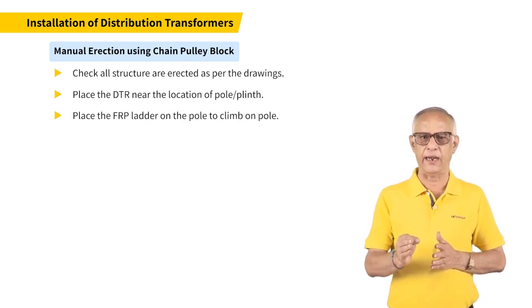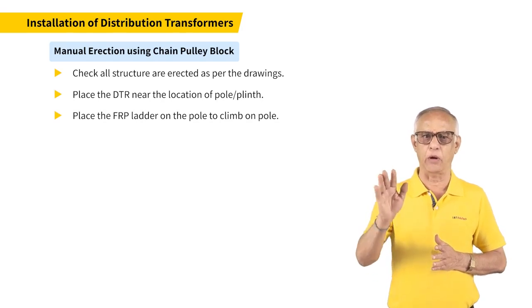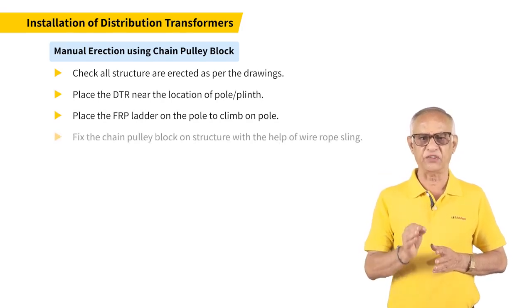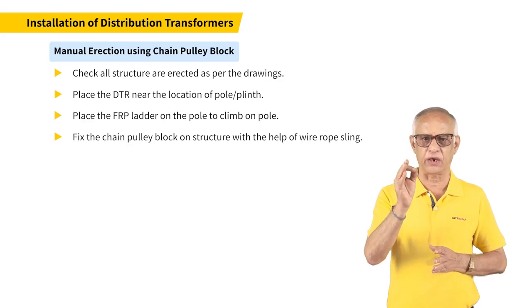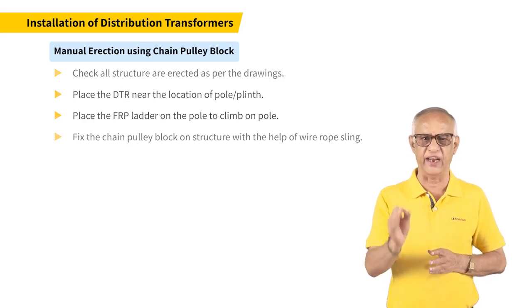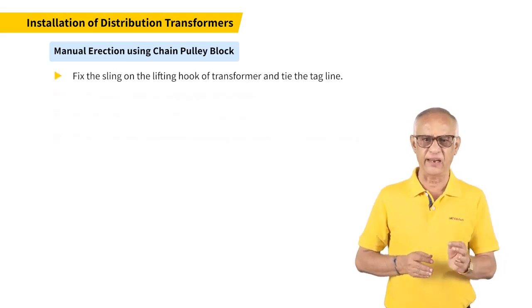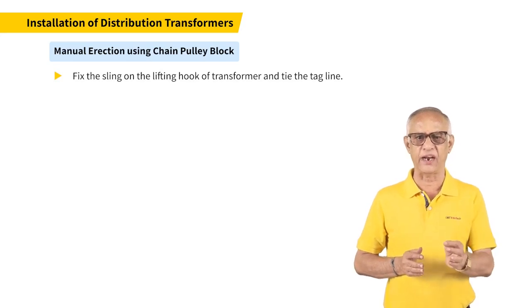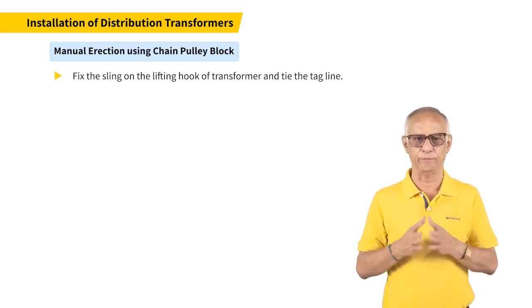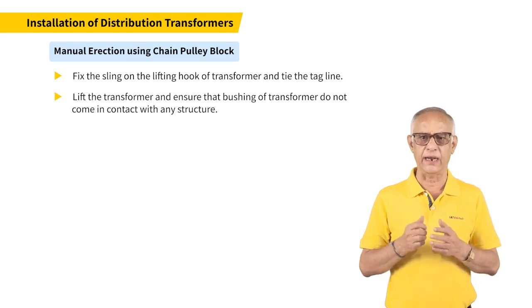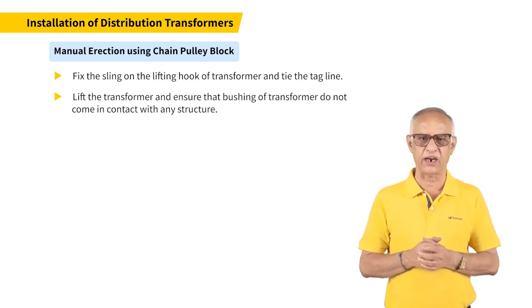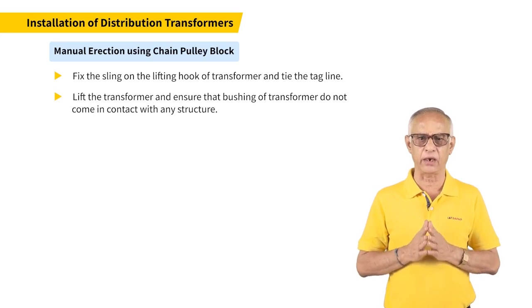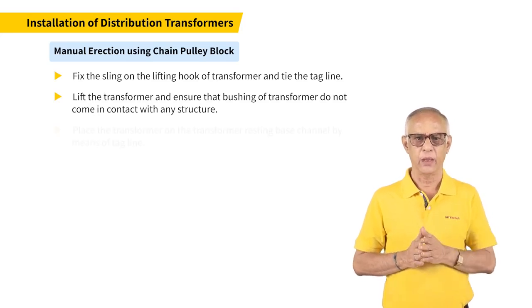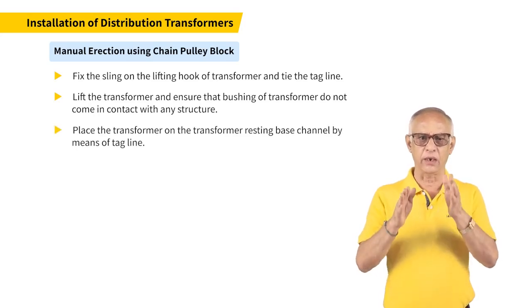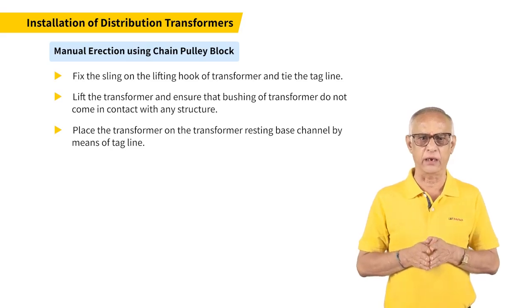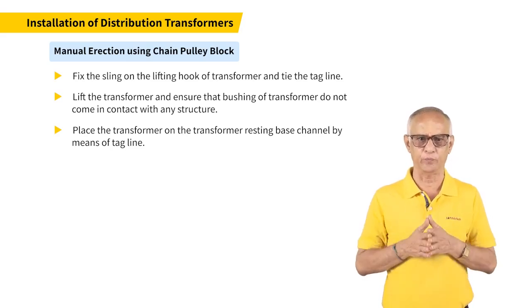Place the FRP ladder on the pole to climb on the pole. Fix the chain pulley block on the structure with the help of a wire rope sling. Fix the sling on the lifting hook of the transformer and tie the tag line. Lift the transformer and ensure that the bushing of the transformer does not come in contact with any structure. Place the transformer on the transformer resting base channel by means of the tag line.